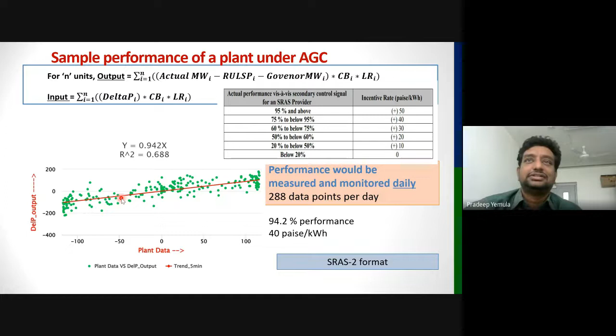You're working on the area control error, right? Yes, area control error. So how do you convert the area control error output to individual generators? That is called the participation factor — we use something called custom participation factor, dividing it among generators based on constants that are updated regularly. We look at the ramp rate and variable cost, and if a power plant is very cheap and has a high ramp rate, we start with that and fill it in.